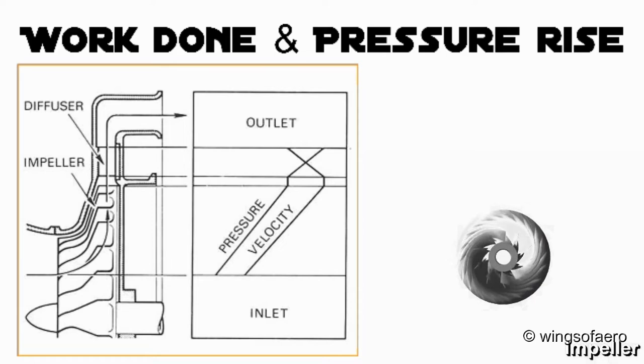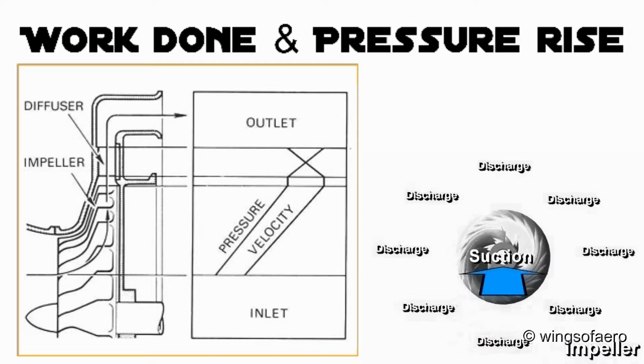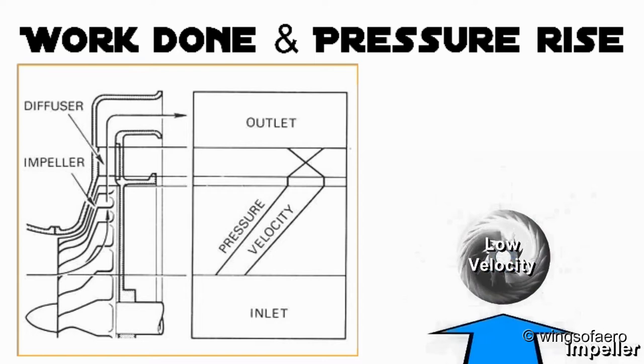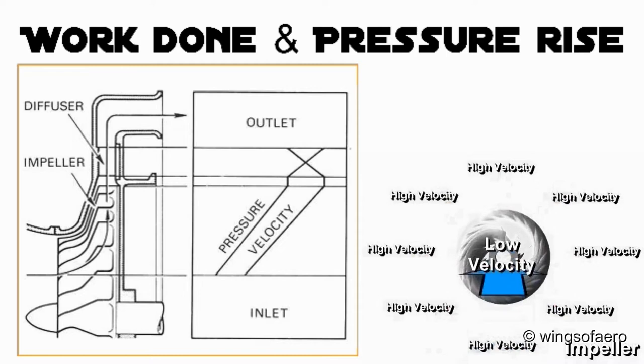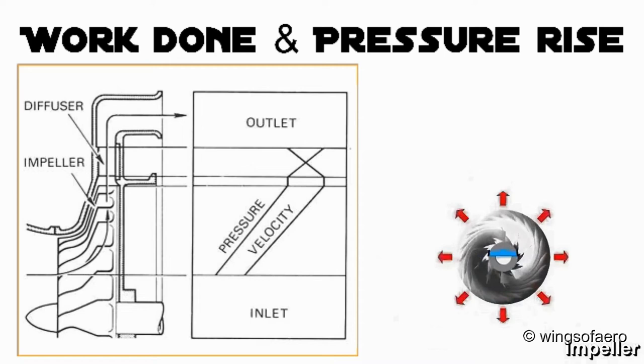As the impeller rotates, the fluid is drawn into the blade passage at the impeller eye. At the center of the impeller, the inlet flow is axial, and the fluid enters the impeller with very little radial or tangential component of velocity, flowing outward in the direction of the blades. The fluid receives energy from the impeller while flowing through it and is discharged with high pressure and velocity into the casing.